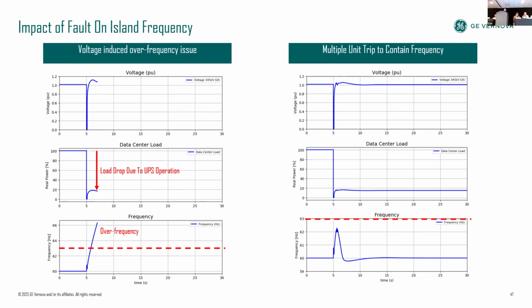Fault ride-through is a critical topic from the load point of view. At least at this point in time, we do not know of a solution or an efficient solution. So one way is to mitigate through some operational means that you have within the plant itself. In this particular case, we allow the unit to trip to save the system so that we can restart again from the available units. So this AI-induced load fluctuation, the frequency and the UPS, is one of the two critical issues that we see today that impact system performance.